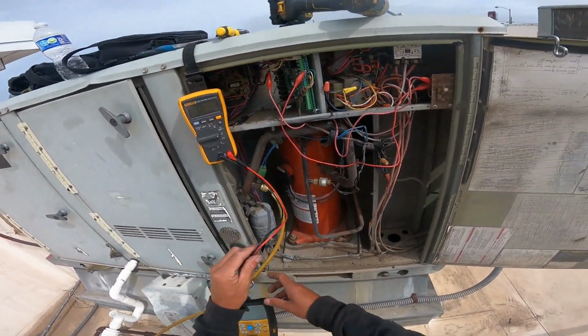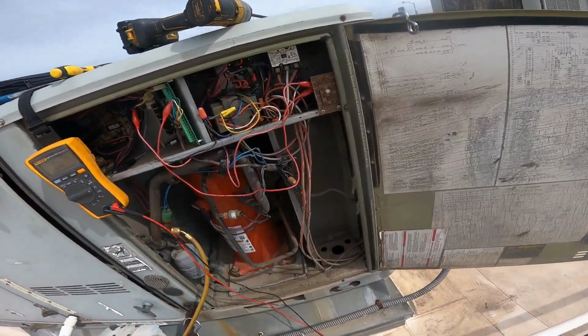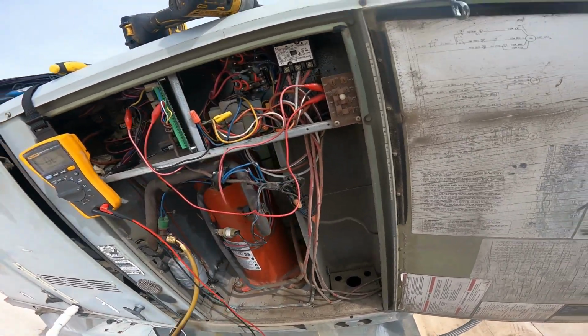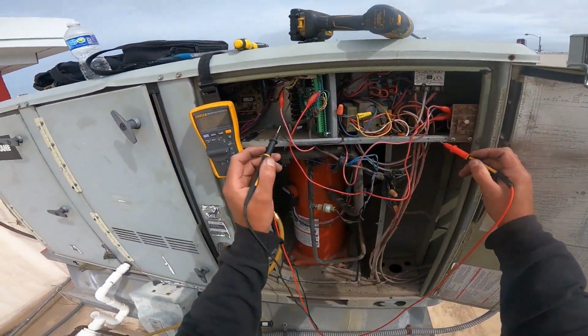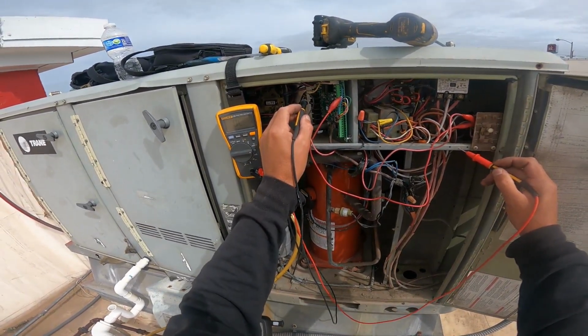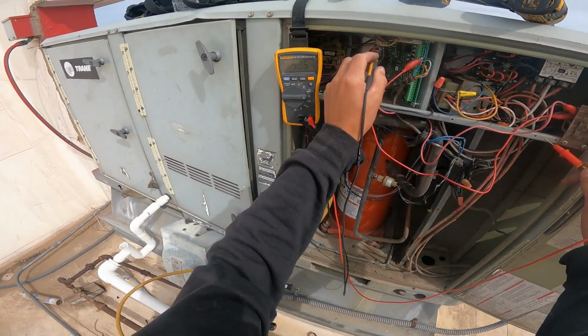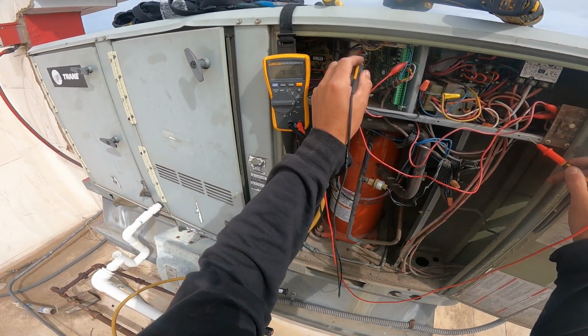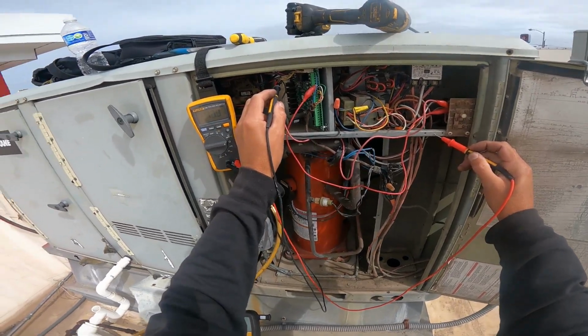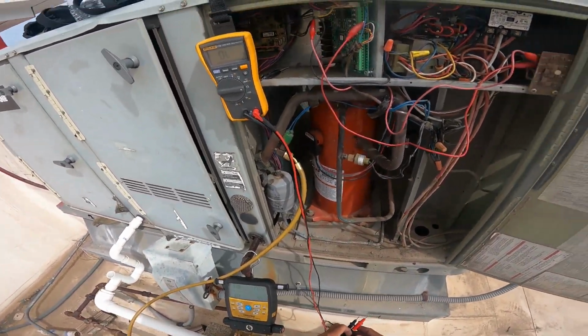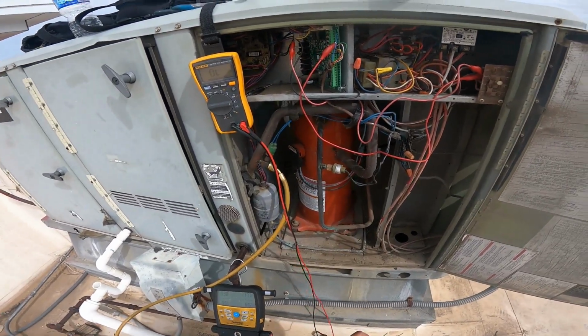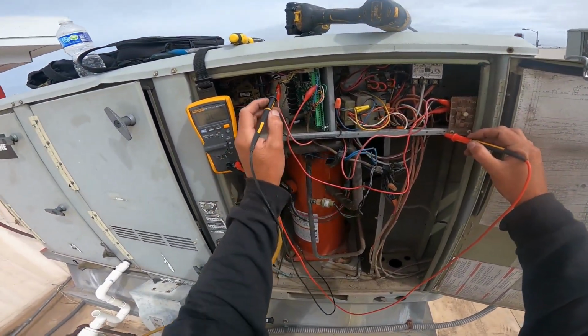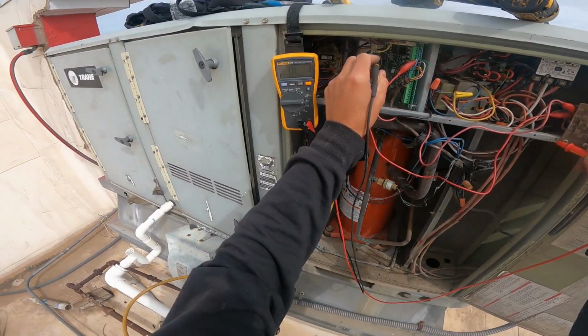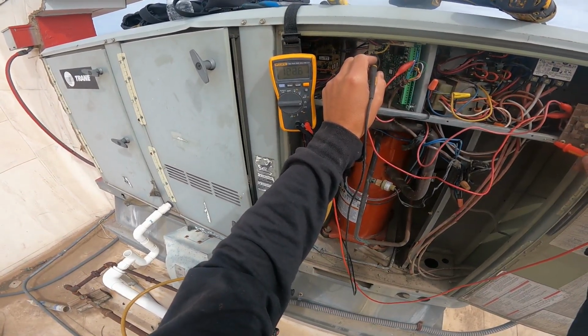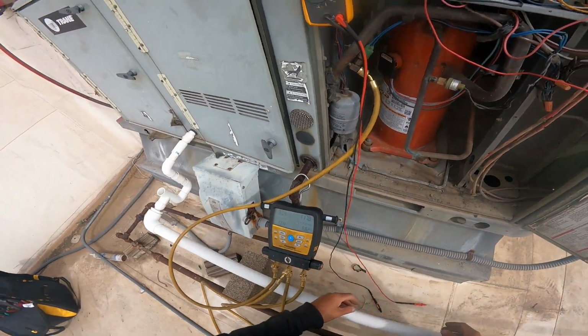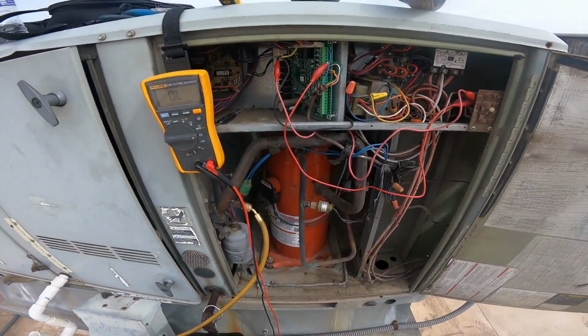But I am not getting something to the contactor, whatever that may be. I have way too many volts, way too many volts. I bet you the coil on that contactor's blown, because this is supposed to be 24 volts. This thing is showing 120. Oh my gosh, people, what did y'all do?